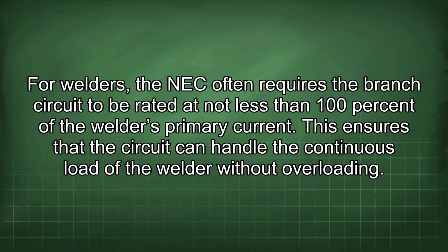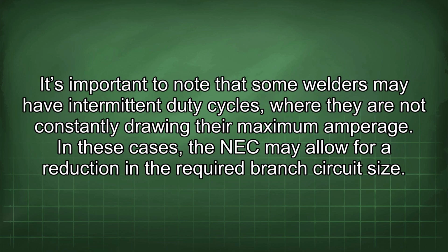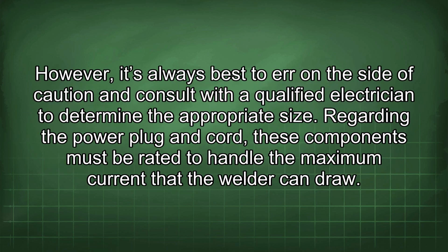For welders, the NEC often requires the branch circuit to be rated at not less than 100% of the welder's primary current. This ensures that the circuit can handle the continuous load of the welder without overloading. It's important to note that some welders may have intermittent duty cycles where they are not constantly drawing their maximum amperage. In these cases, the NEC may allow for a reduction in the required branch circuit size.